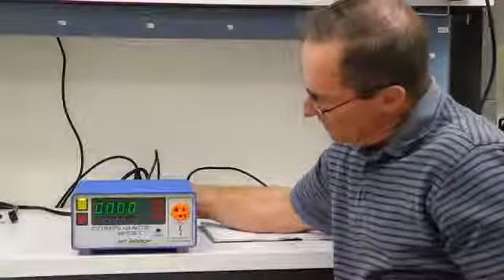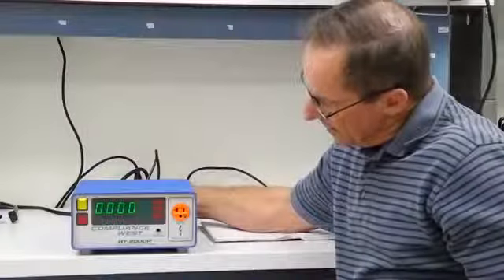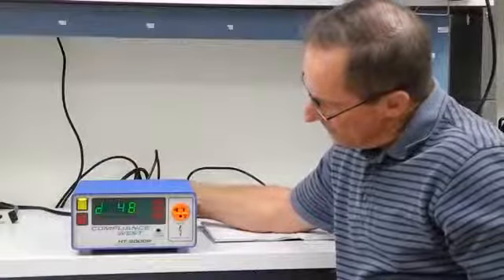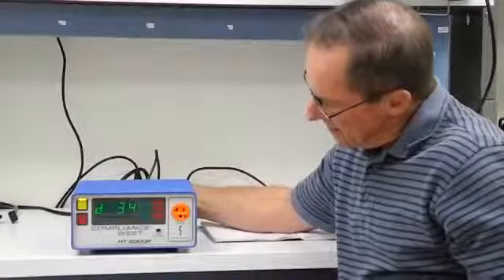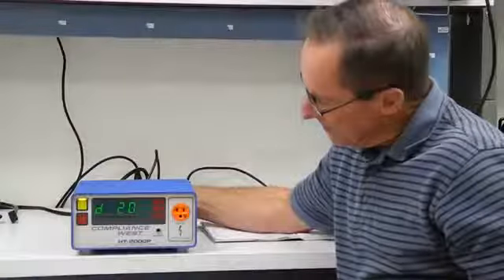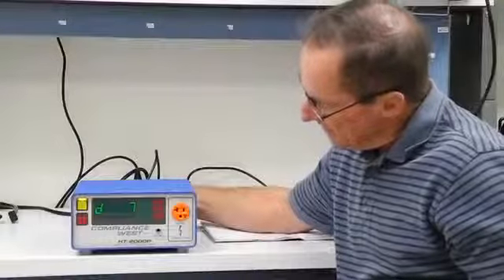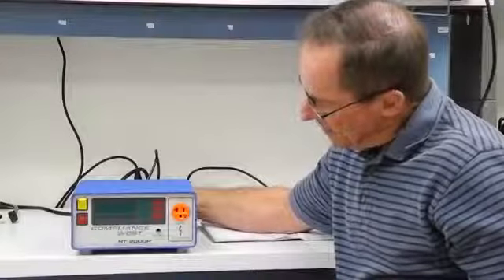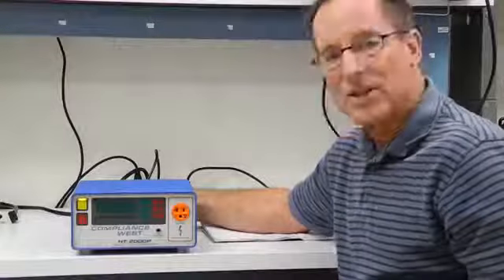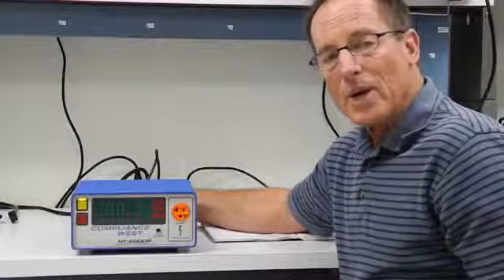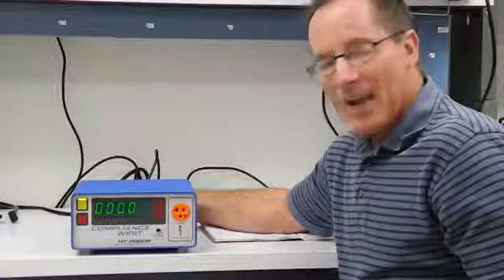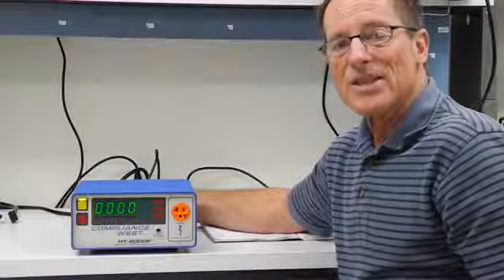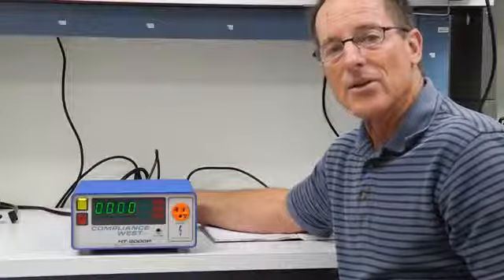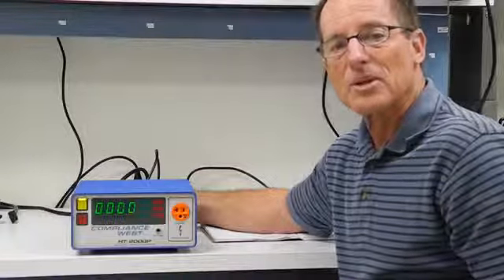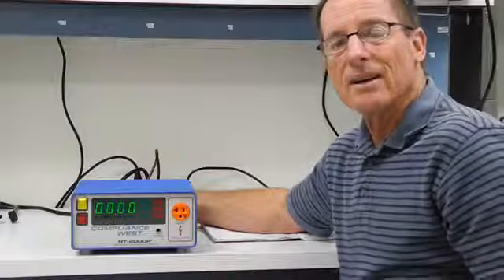So I'm going to move the middle one. Right now we're at 48 seconds because we set it high to set the voltage. Coming down. There we go, 1 second. Now, every time that you hit the button, it will ramp up to 1200 volts, and then it will hold that 1200 volts for 1 second. It's going to watch for 2 milliamps or less. If it pops over 2 milliamps, you're going to get a failure.